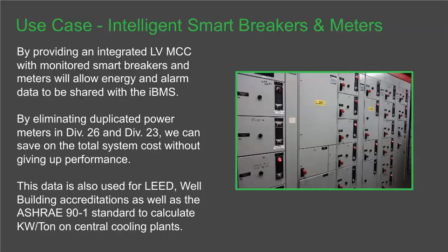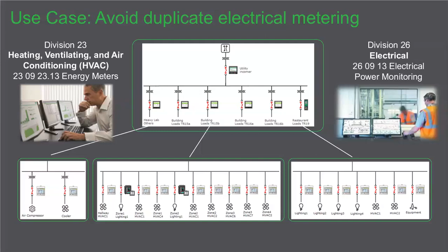An example would be where you typically had duplicate information - it's very common that Division 23 and Division 26 don't always communicate in coordination. I've seen many times where power meters come right on the gear, maybe not down to the breaker level, but at least the station or MCC level, and then you also have duplicate meters downstream that bring you a lot of the same data. If you can combine more of that into the breaker side and get it from the factory already installed, that saves a lot of information.